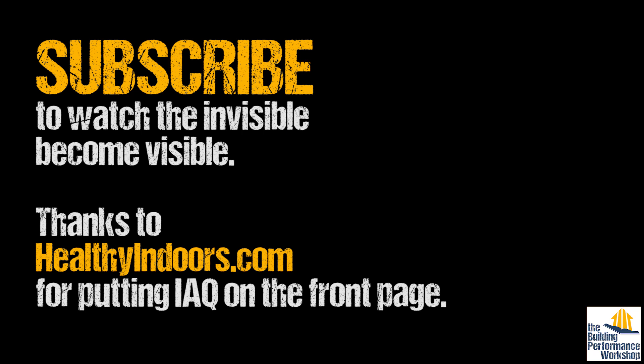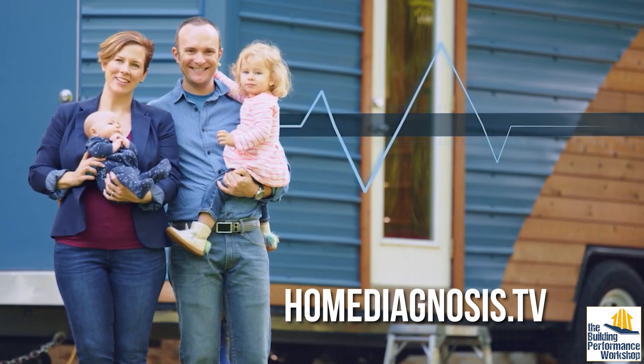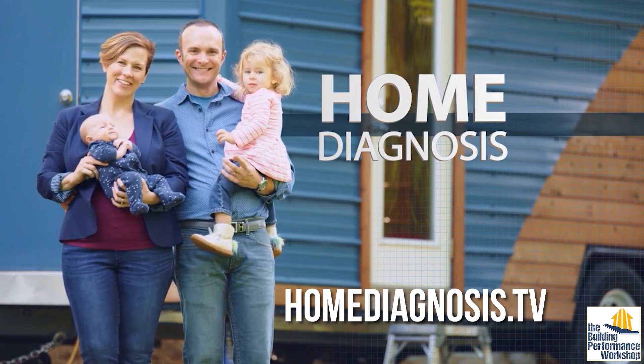The ERV is probably more than enough for what we need, but in the case of a little girl party or a laser tag party with a bunch of stinky adult men, we might want to activate the HEPA unit. The HEPA unit runs 240 CFM, which is close to changing out all the air in the room once per hour. That HEPA unit is going to pick up both VOCs and odors with a charcoal filter, and also particles — a lot of particles. It filters out 99.97% of particles down to 300 nanometers in size or bigger, and probably smaller than that too, though they don't measure for that with HEPA certification.